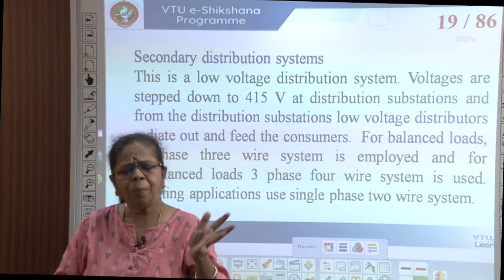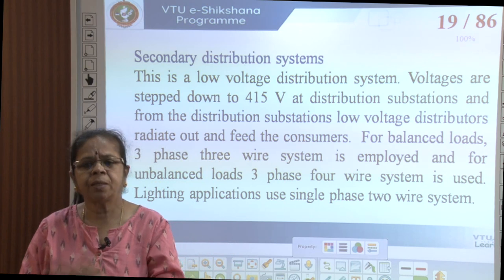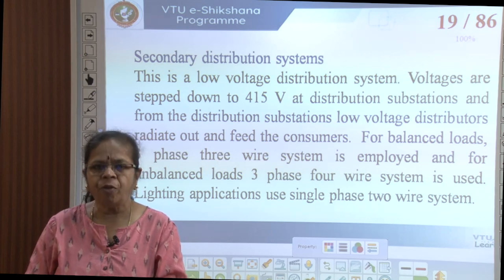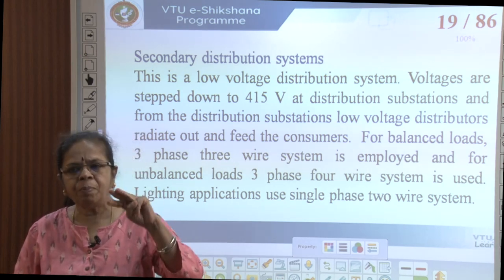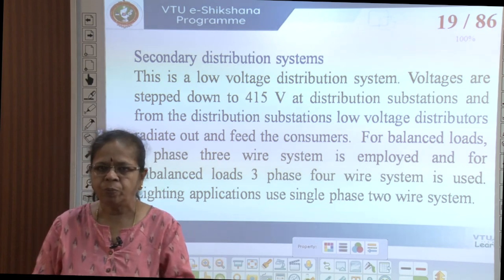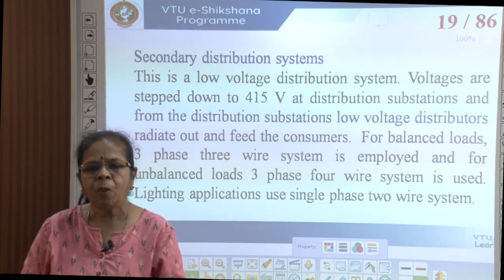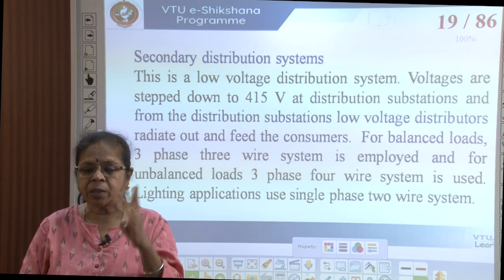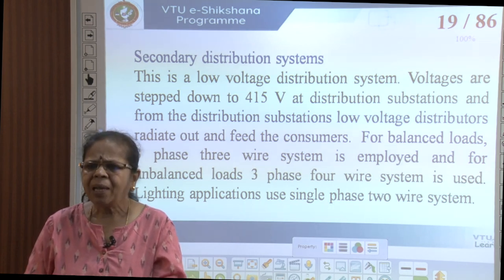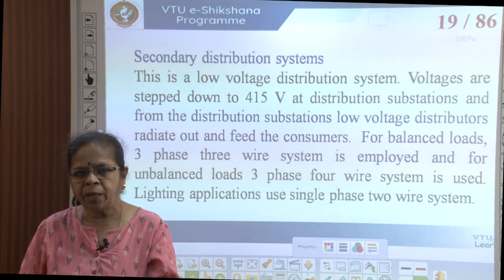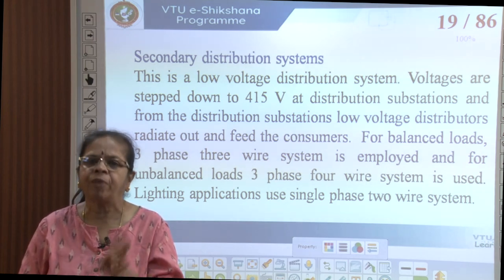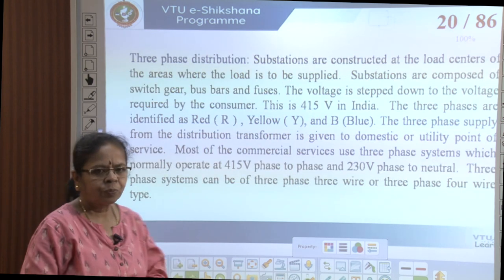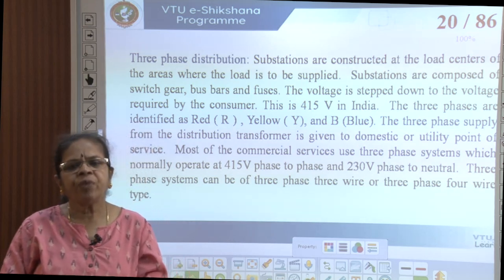Coming to the secondary side — direct at the consumer level — it is low voltage distribution. The voltage is stepped down to 415 volts 3-phase, which is the line-to-line voltage. Three-wire systems are used for balanced loads and 4-wire systems for unbalanced loads. Lighting and most single-phase loads take single-phase supply, which is supplied to lighting equipment.